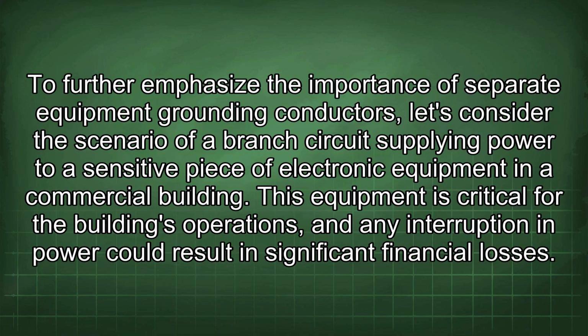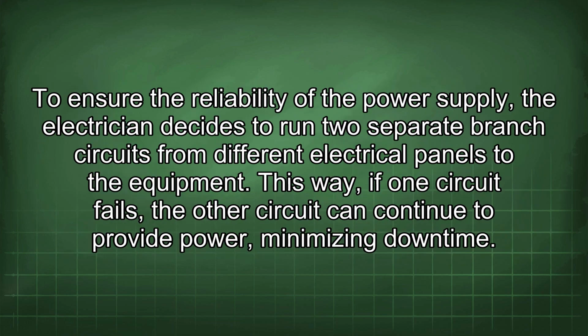To further emphasize the importance of separate equipment grounding conductors, let's consider the scenario of a branch circuit supplying power to a sensitive piece of electronic equipment in a commercial building. This equipment is critical for the building's operations, and any interruption in power could result in significant financial losses. To ensure the reliability of the power supply, the electrician decides to run two separate branch circuits from different electrical panels to the equipment. This way, if one circuit fails, the other circuit can continue to provide power, minimizing downtime.